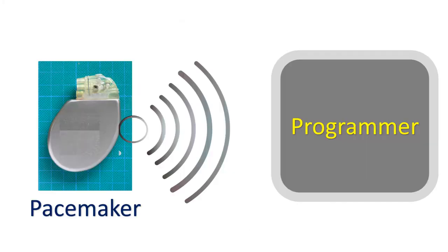Modern pacemakers are communicative pacemakers as well. They can communicate with special devices kept near the person using radio waves. The device is known as pacemaker programmer, which can analyze the function of the pacemaker as well as give instructions to the pacemaker to change its pacing rate, pacing sequence, and pacing voltage output. The pacemaker programmer can be connected to the internet and the information can be transferred across the globe to get opinion from experts elsewhere in case there is a difficult pacing problem.